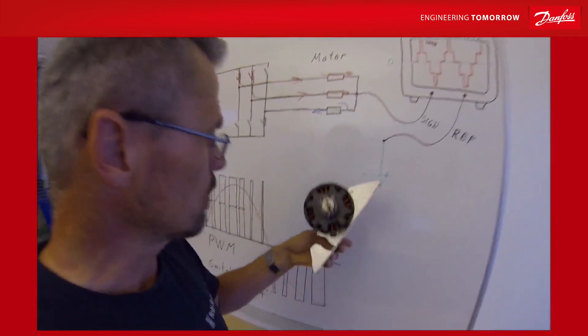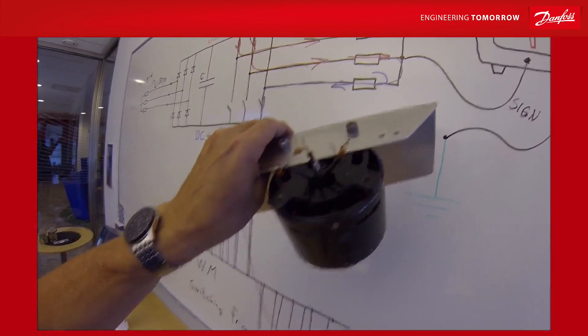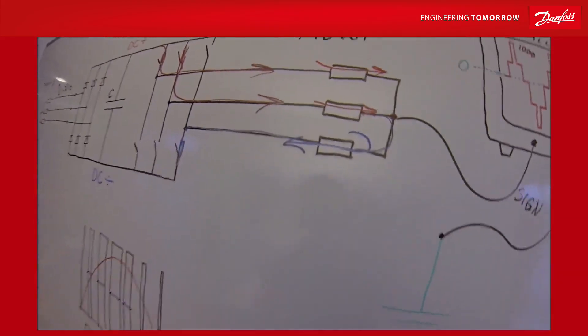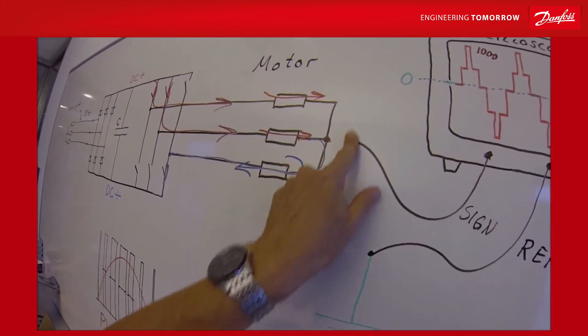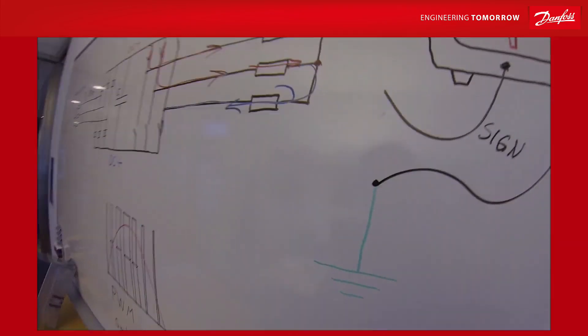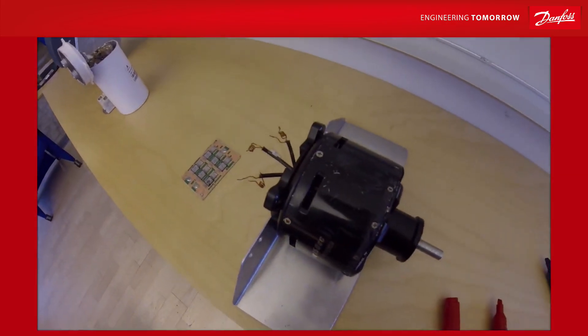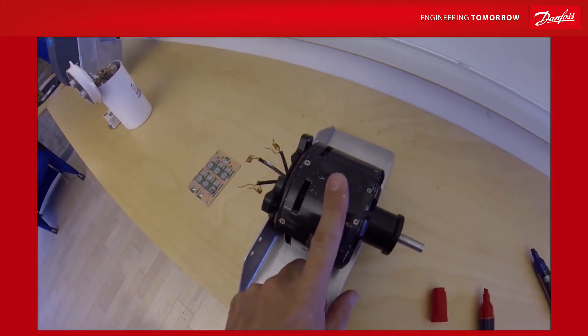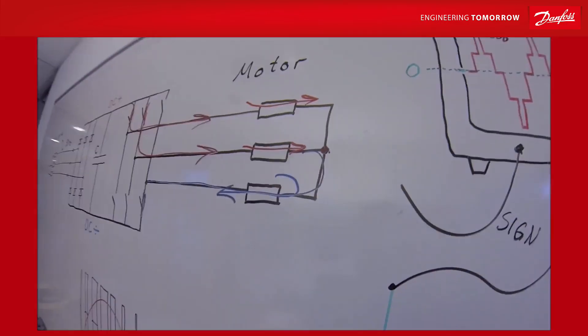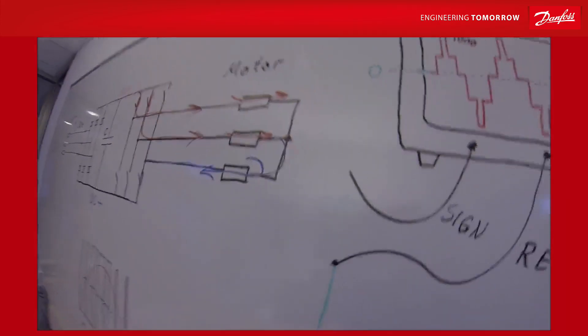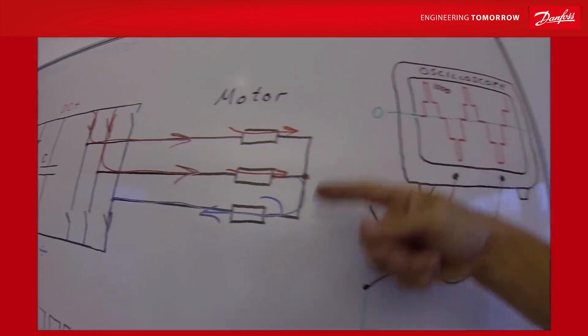What is the consequence on a motor when you have a star point which is jumping up and down? Well, actually not much, because this star point is floating inside all motors. There is no connection between this star point and the metal in the motor, at least not in an ideal world.